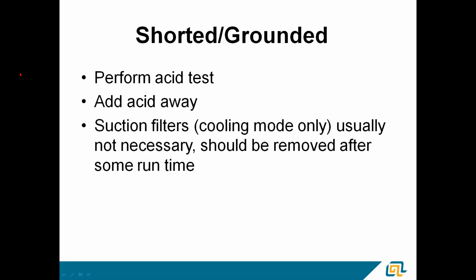The problem with suction filters is they're very, very, very good cleaners. They will scrub all kinds of debris out of that system that there is. But in doing so, they get restricted. If you have a 3-degree drop across a filter, you've got a restricted filter, whether it's suction or liquid.